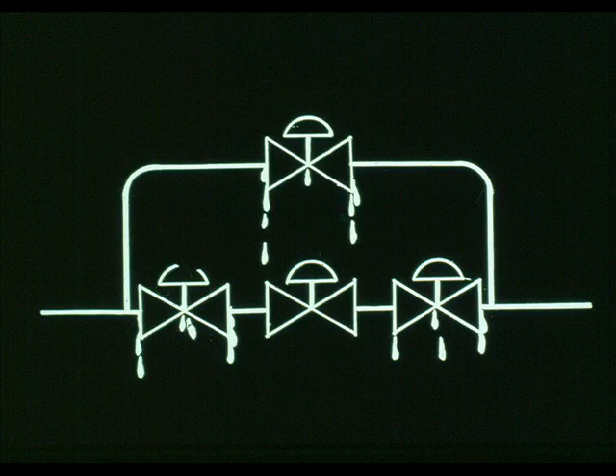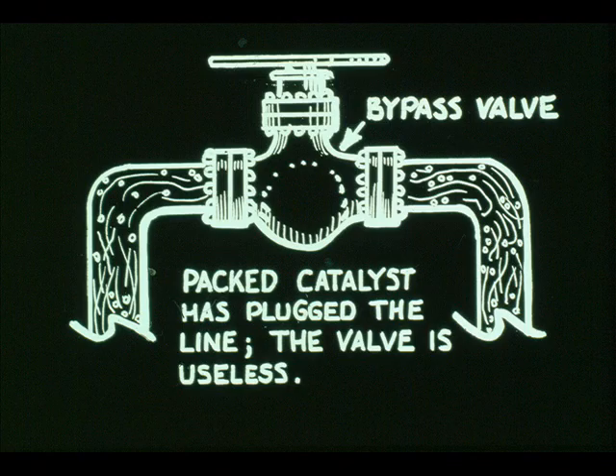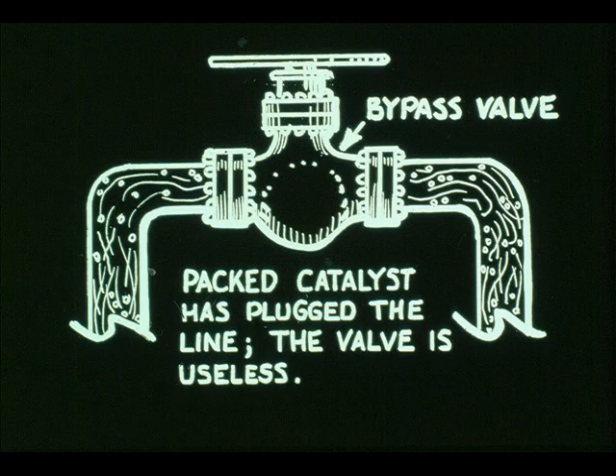Applications where it is desirable to reduce the leak source of hazardous fluids such as hydrogen, phenol, and acid do not require a bypass or blocks. In slurry or particulate services such as lime or fluid catalyst, the process media will plug any line where there is no flow, which would render the bypass useless, so it is omitted in these types of service.